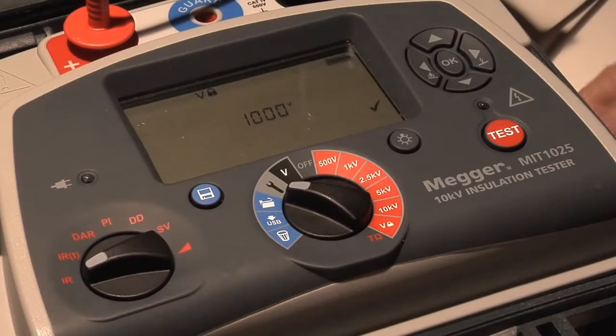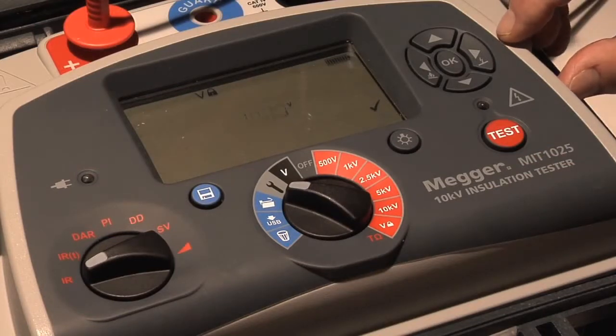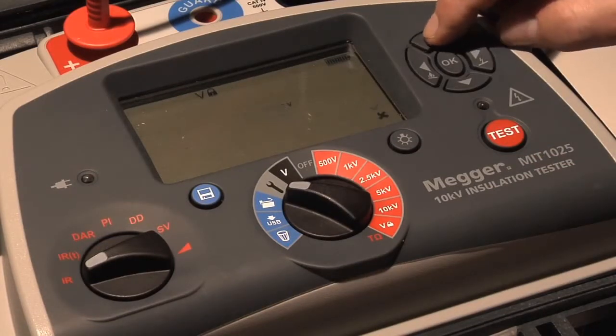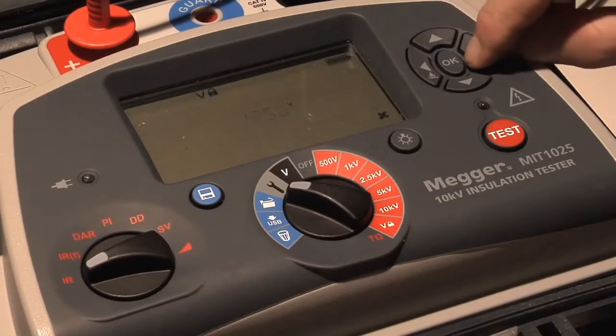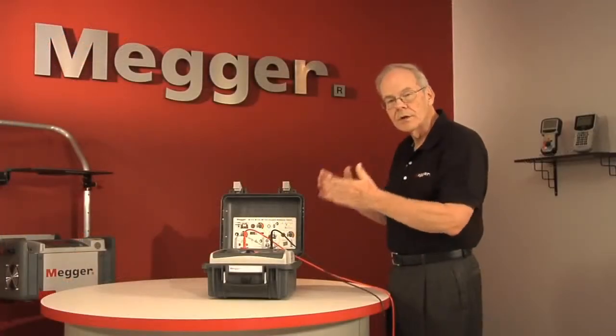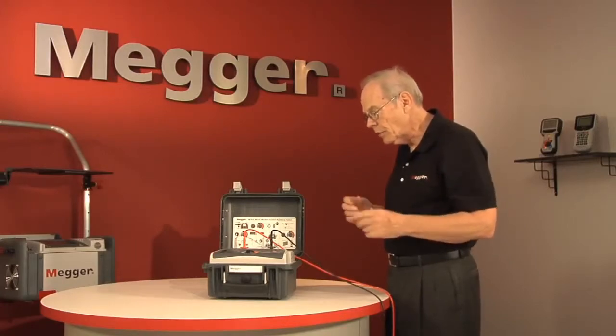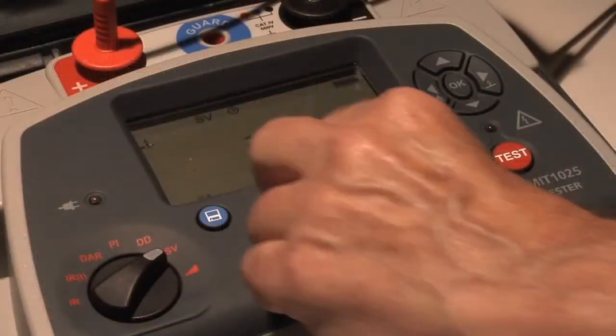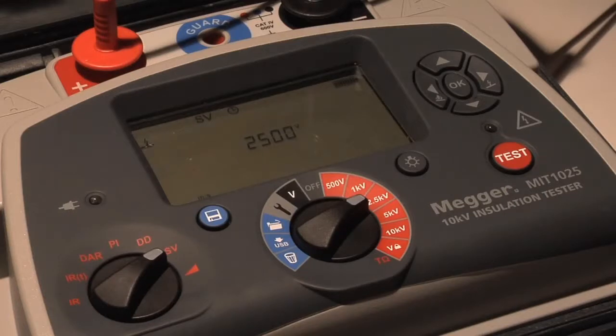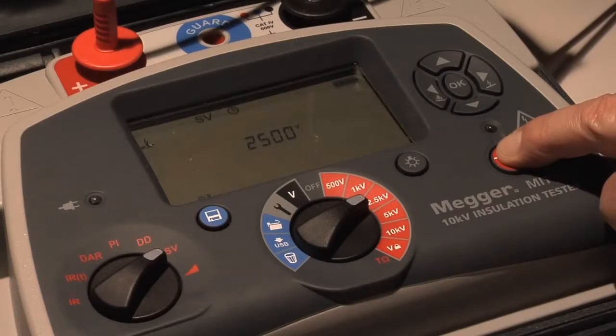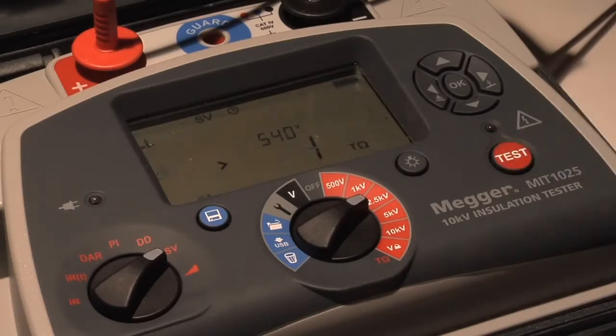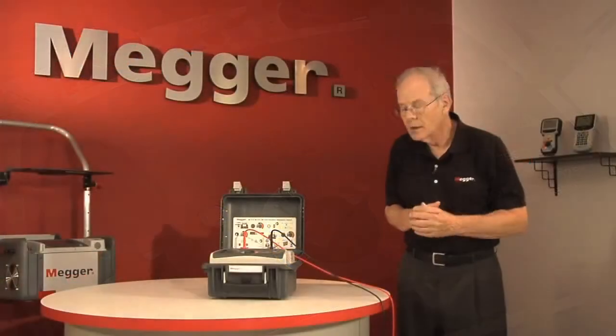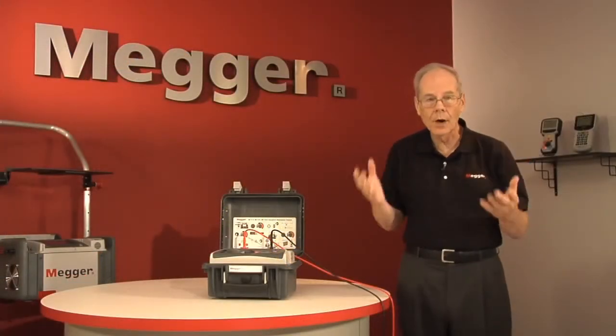So you would start by going to the setup menu, and let's say you wanted to run a 10 kV test. So using your keys here, you would establish the voltage ceiling that you want to run to, and then from there you would hit the selected test voltage and the test button again and energize the test. And now everything else is going to run automatically from this point on, and what the tester will do now is run the first voltage for 1 minute.